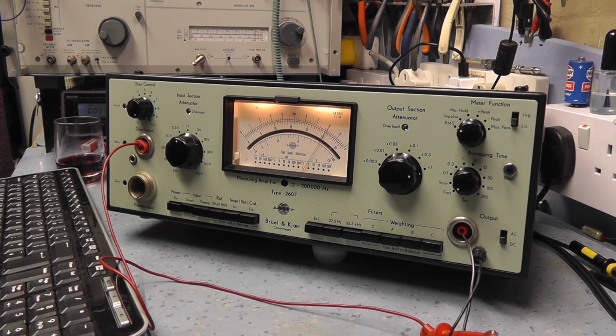I don't know why the meter dropped back like that. That would imply that there is actually something wrong with this instrument. Just looking at the responses now. Yeah, it's got quite a significant roll off for some reason. I'm not sure why. I think there is actually a problem with this unit. In theory, it should be flat from 2 Hz to 200 kilohertz, and certainly the output I'm looking at the moment doesn't look like it is. So let it run through. We are now at 63 kilohertz.